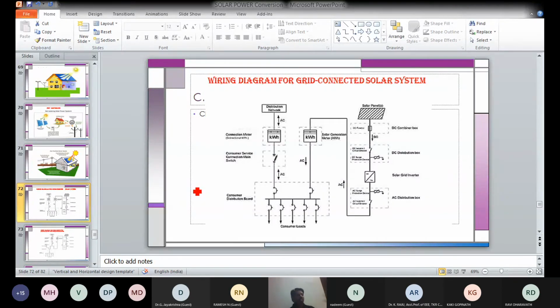What will happen when grid power is off? When grid power is off, there won't be any reference - zero reference frequency and zero reference voltage will come. If that condition happens, it has to automatically turn off and stop supplying power to the grid.